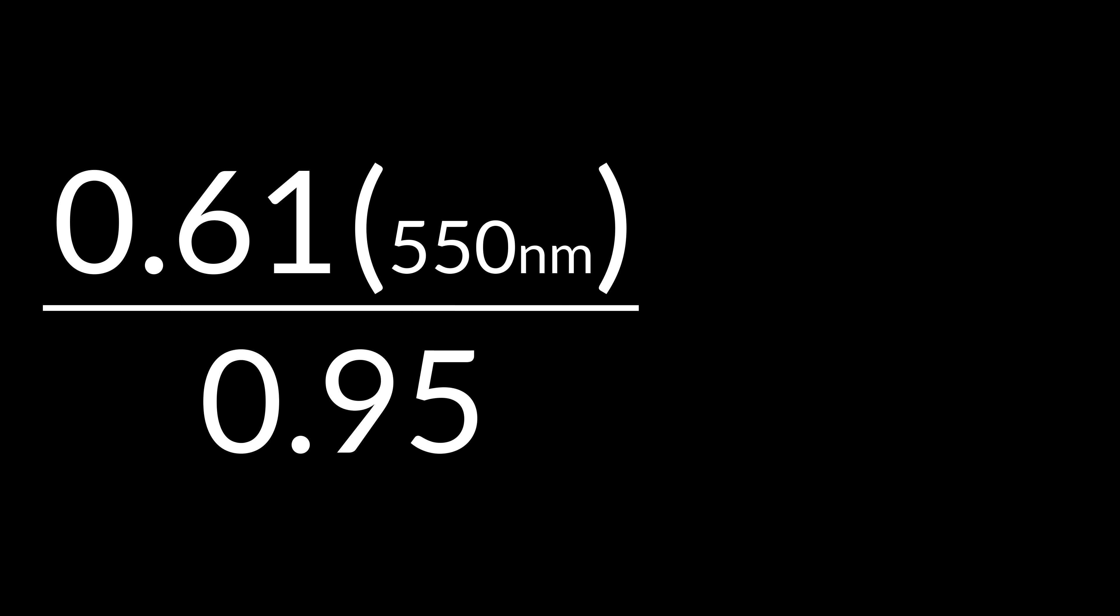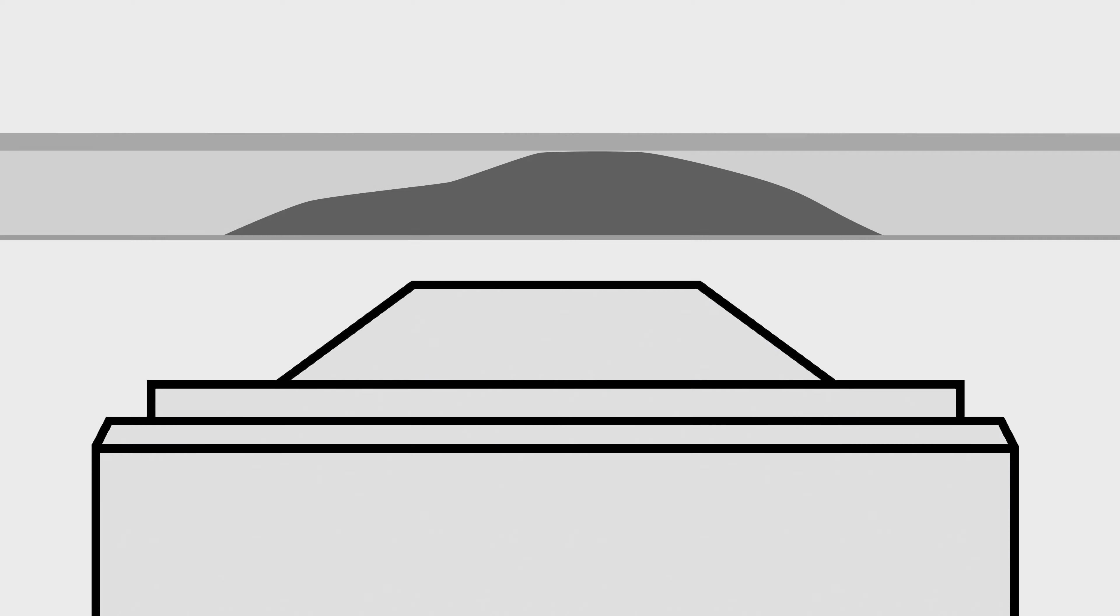According to the Rayleigh criterion, the best resolution we can achieve with this NA would be approximately 350 nanometers. If our experiments require a higher resolution than this, we'll need to use a lens that is designed to use a higher refractive index medium between the coverslip and the objective.